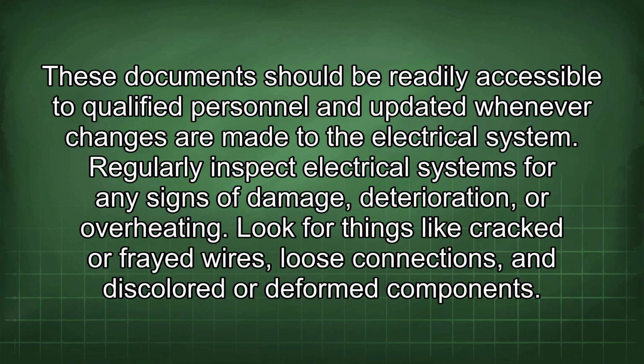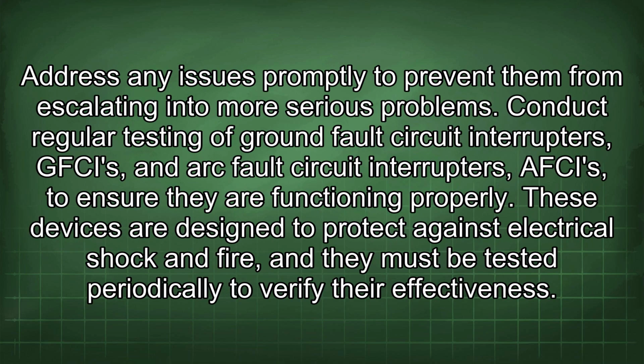Regularly inspect electrical systems for any signs of damage, deterioration, or overheating. Look for things like cracked or frayed wires, loose connections, and discolored or deformed components. Address any issues promptly to prevent them from escalating into more serious problems. Conduct regular testing of ground fault circuit interrupters, GFCIs, and arc fault circuit interrupters, AFCIs, to ensure they are functioning properly. These devices are designed to protect against electrical shock and fire, and they must be tested periodically to verify their effectiveness.